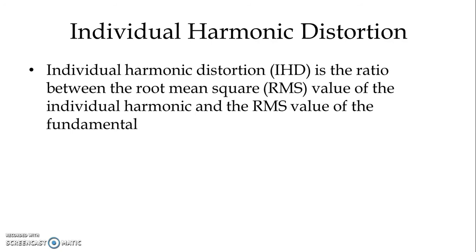Individual harmonic distortion, normally indicated as IHD, is the ratio between the RMS value of the individual harmonic and the RMS value of the fundamental. So when we calculate the individual level of harmonic distortion at each harmonic number or harmonic frequency, it is the ratio of the RMS value of the individual harmonic to the RMS value of the fundamental wave.